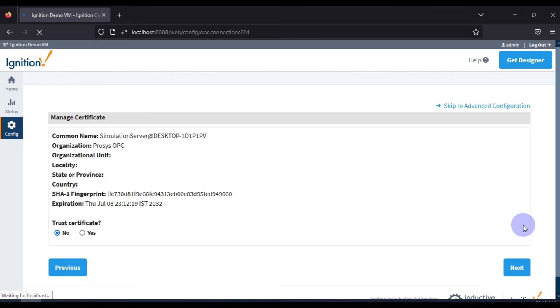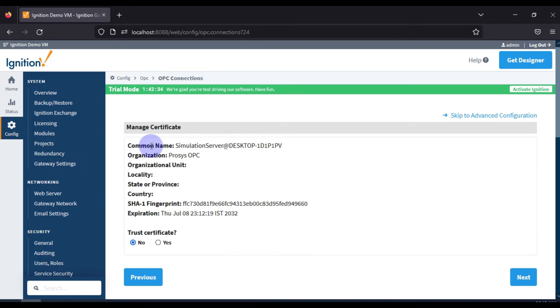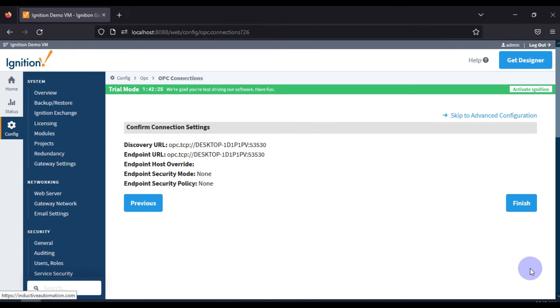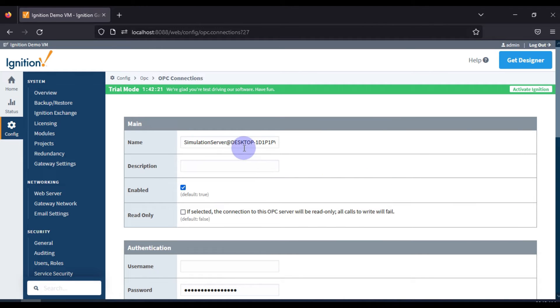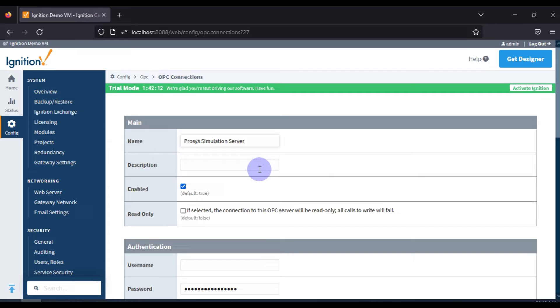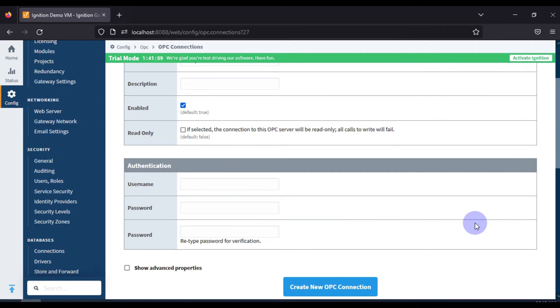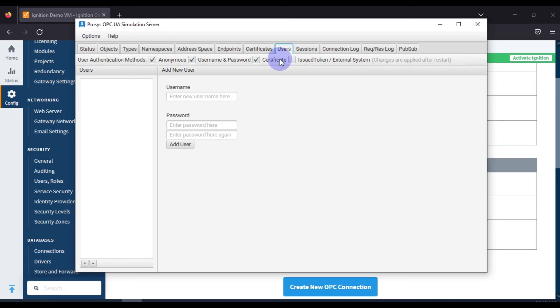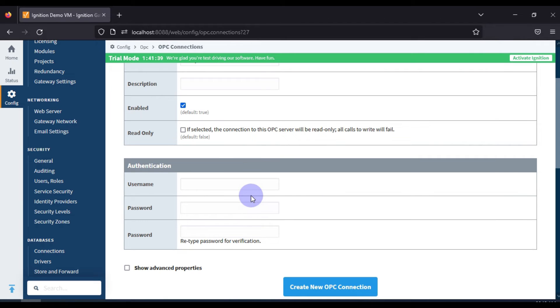After pressing Next, we see information about our OPC UA connection and we have to trust the certificate by selecting the 'Yes' radio button, then press Next and Finish. The default name is available — we can modify it to 'Prosys Simulation Server'. We also need to remove the password since we didn't create any user for this OPC UA simulation server. You can add users with passwords for restricted access, but for this simple setup we don't need any credentials. Then press 'Create New OPC Connection'.